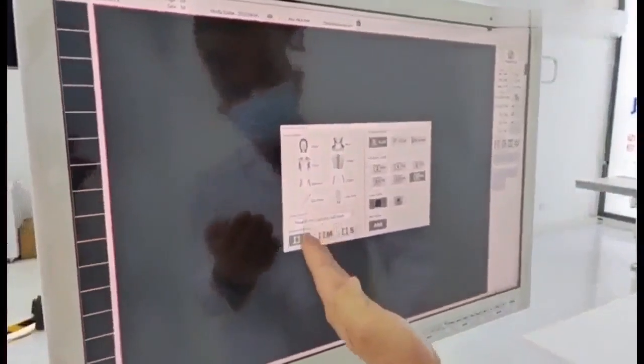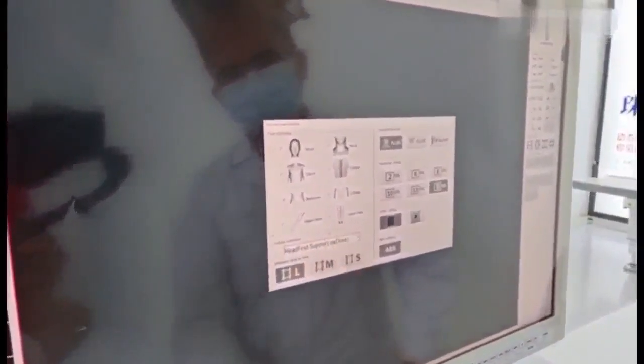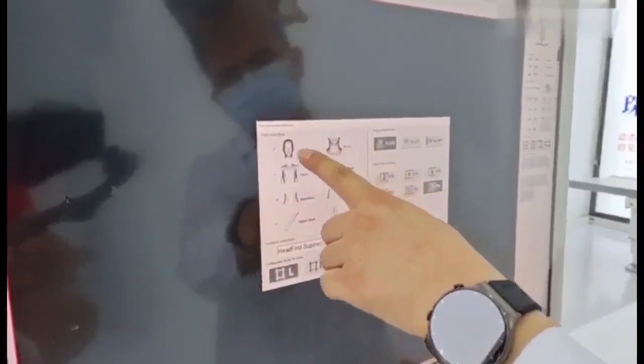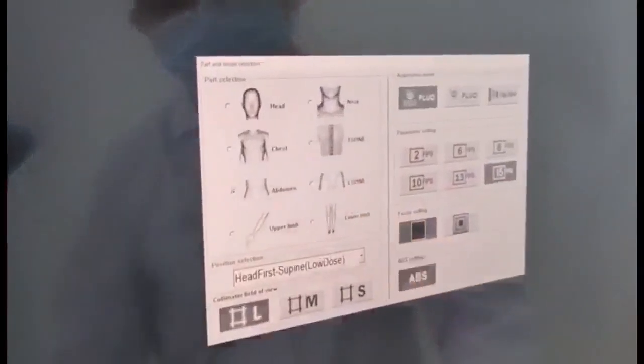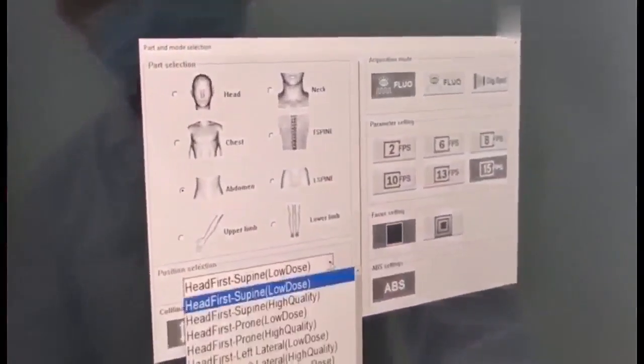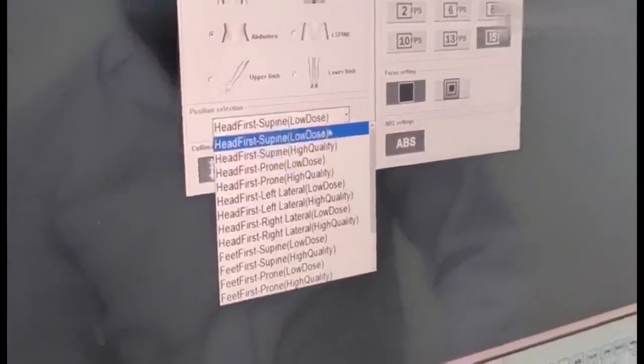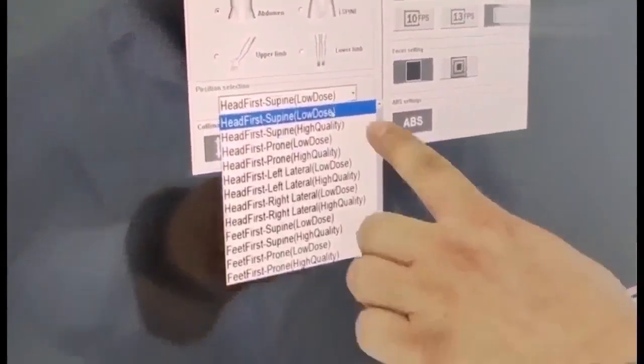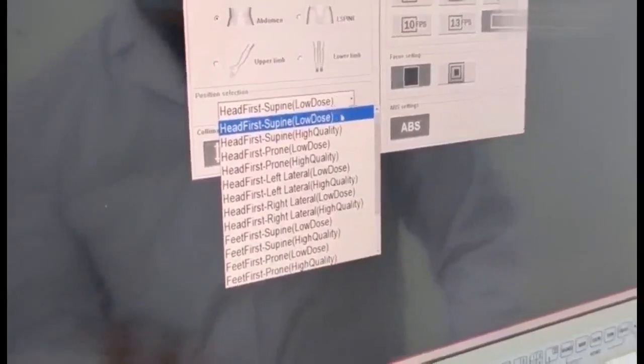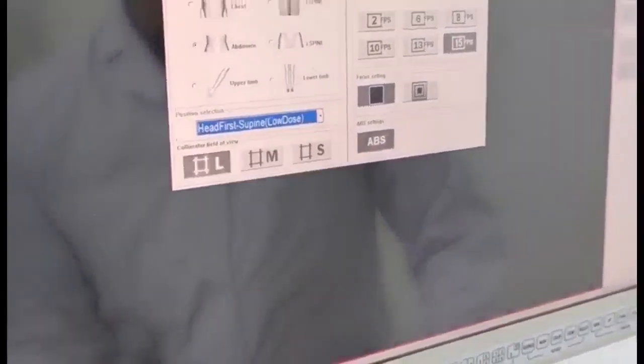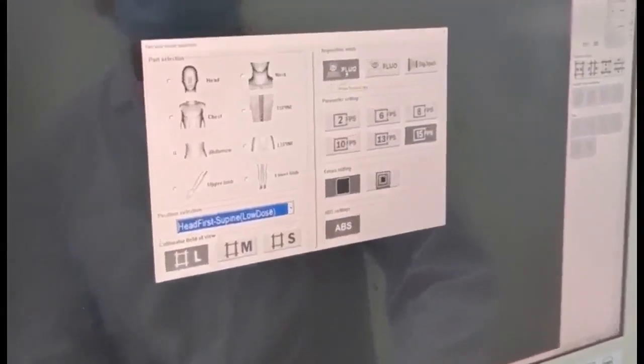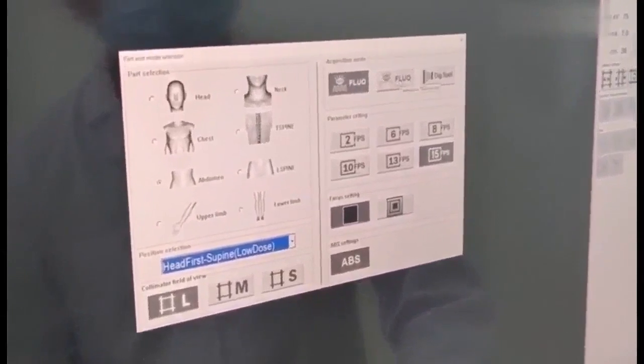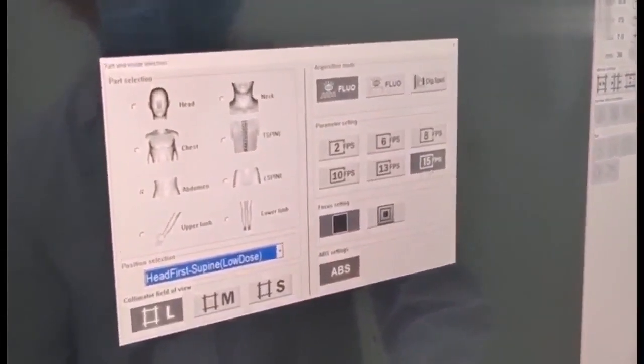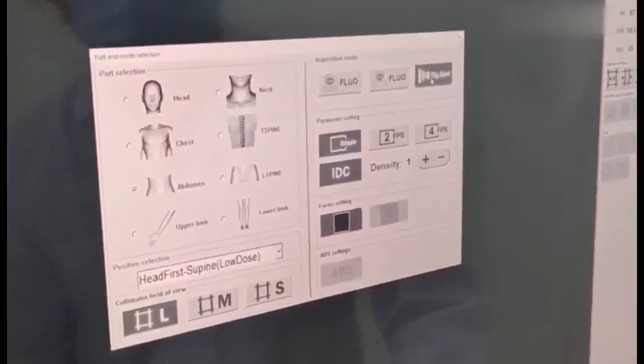Okay, after registration is the image acquisition part. You choose the body part: spine, C-spine, head or lower limb. After choosing the body part, there are 4 different views: up, down, left and right. In each view of a certain body part, there are 2 models, low dose or high image quality. You can choose according to your own surgery needs. For the collimator, most of the time we use the large collimator. We have 2 fluoroscopy modes, pulsed fluoroscopy and continuous fluoroscopy. Also, we have the spot film mode.